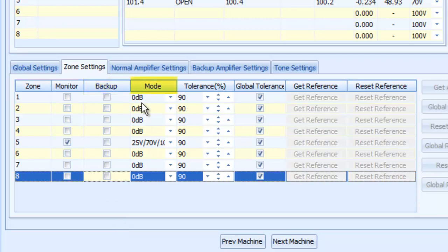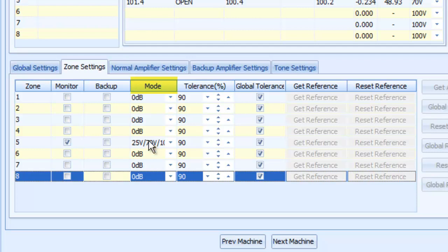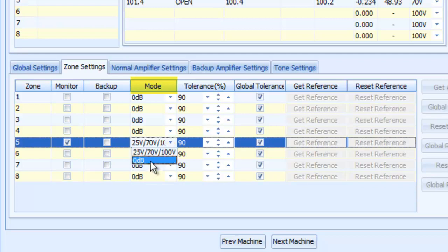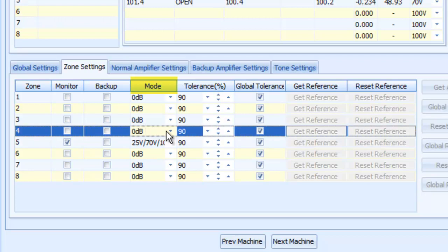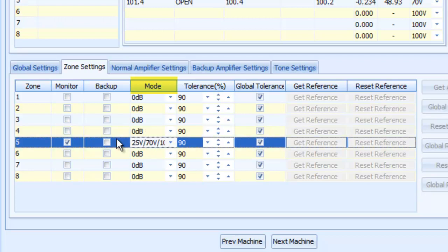Also the mode, 0 dB is if you're feeding the balance line output to an amplifier, but the amplified return is not coming back through the IDA8 for supervision. If that is the case, then just leave it at 0 dB, which means monitoring will be turned off for that circuit. If you are using it in distributed mode, just make sure you check it for distributed 25, 70, or 100 volt. That's just the distributed mode, as you can see right here. So I got my circuit 5. I'm set up for that mode.